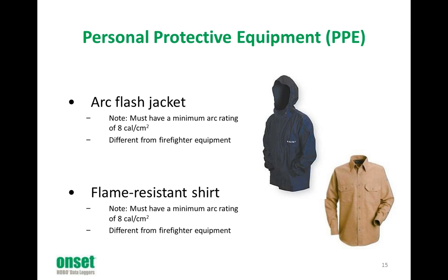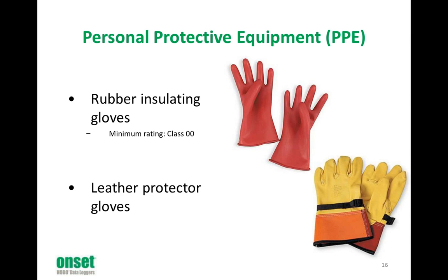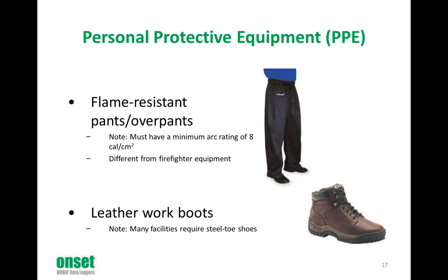You then need an arc flash jacket, again, the same arc rating of 8 calories per square centimeter. And you can also wear a flame-resistant shirt having that same rating. You then need rubber insulating gloves for the voltage, and then leather protectors to protect from the heat and puncturing the gloves. Followed by flame-resistant pants and overpants. Again, different from firefighter equipment, and then leather work boots. Many facilities that you work in will require steel toe shoes.